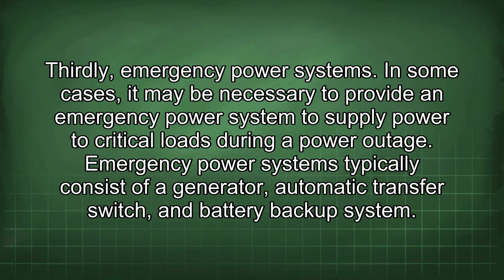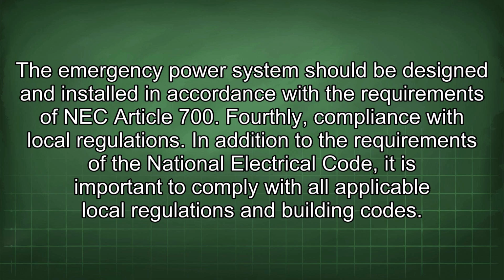Thirdly, emergency power systems. In some cases, it may be necessary to provide an emergency power system to supply power to critical loads during a power outage. Emergency power systems typically consist of a generator, automatic transfer switch, and battery backup system. The emergency power system should be designed and installed in accordance with the requirements of NEC Article 700. Fourthly, compliance with local regulations.